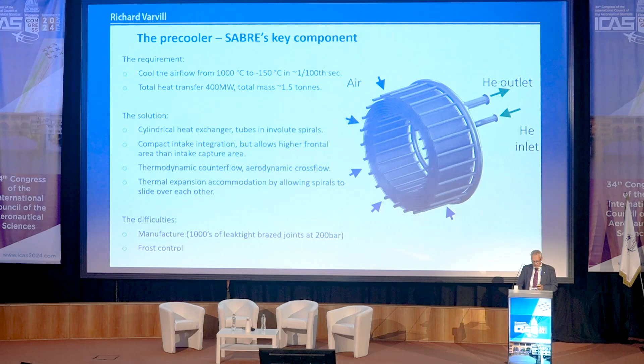So what about this frost control? What's that all about? So as I said, if you cool the air sub-zero, what happens is that any water vapor in the air immediately condenses from the vapor directly to frost without going through a liquid phase, and it blocks the pre-cooler matrix in about 3 seconds flat. And I know that because I've done it. So you have to have a frost control system to prevent that. And the way we do that is to use an antifreeze, which in our case is methanol, which mixes with the condensed water vapor and keeps it as a liquid. So you've actually got a two-phase flow, effectively it starts raining inside the pre-cooler.